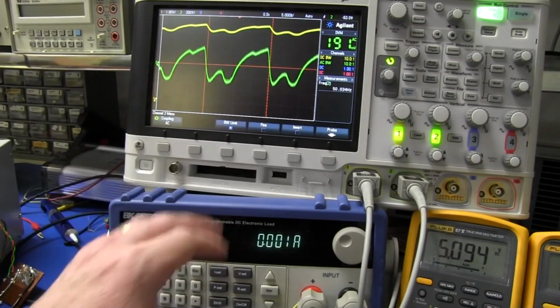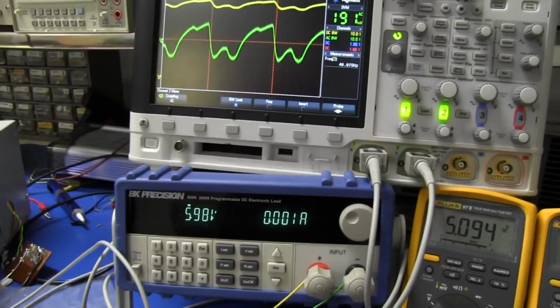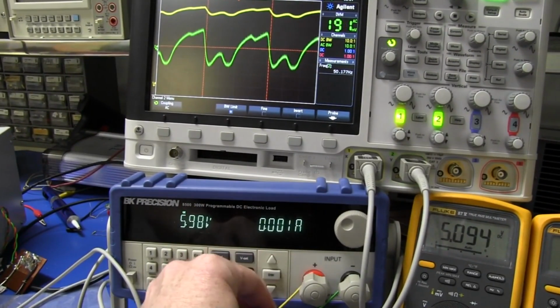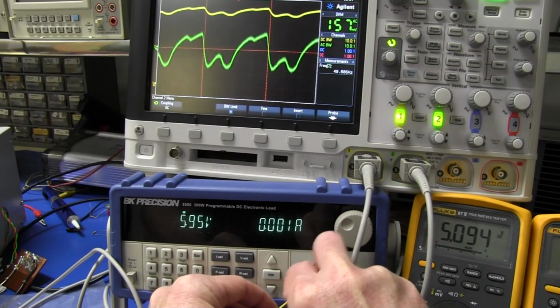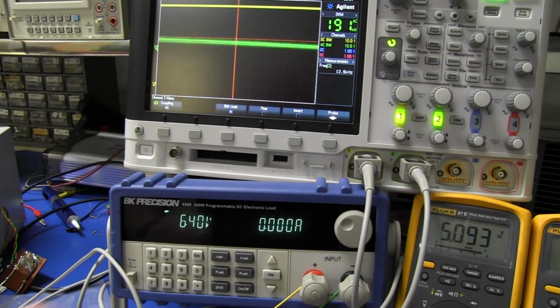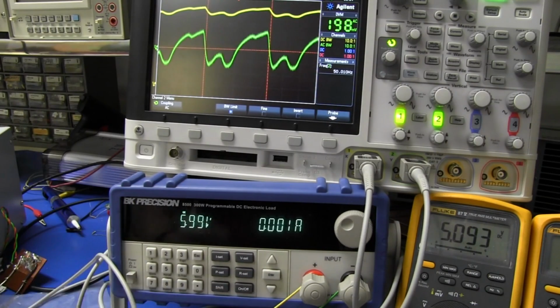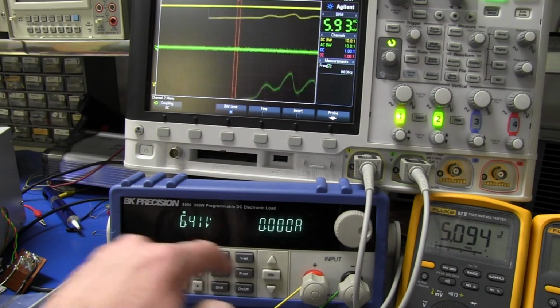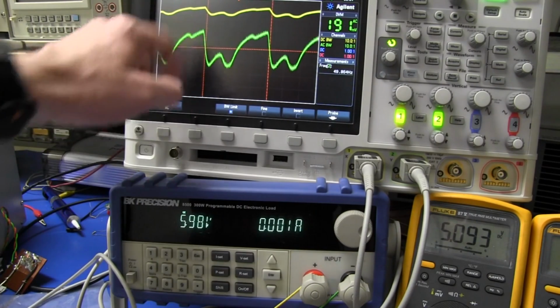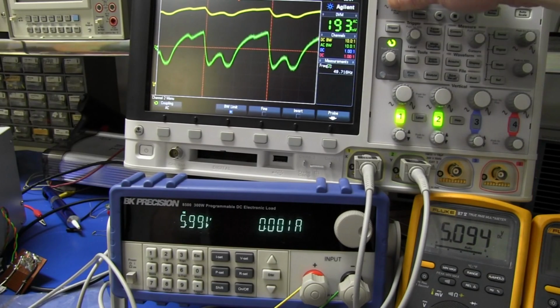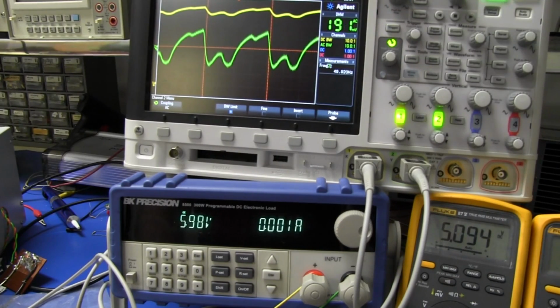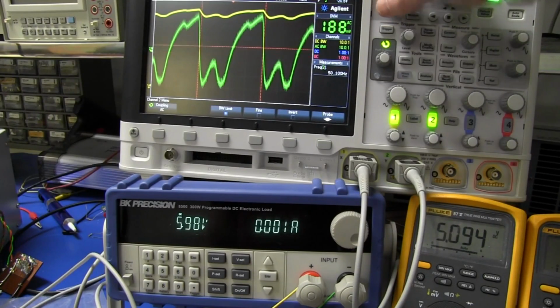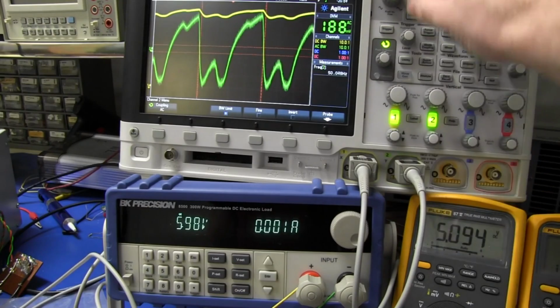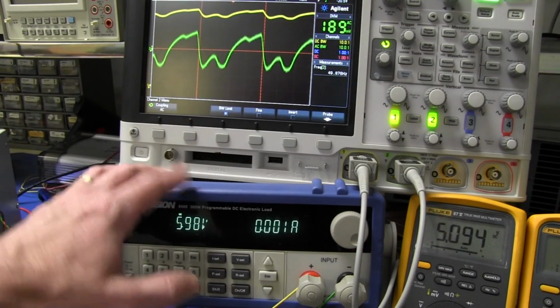Now as for this 50 Hertz issue with this electronic load, it's rather puzzling. If I disconnect it, it vanishes. If I switch it off, it vanishes. There's hardly any load - like 1 milliamp if anything, practically turned down to zero, but it really starts injecting massive amounts. We're talking 200 millivolts per division there, so 0.5 volt of 50 Hertz hum into our measurement system. Unfortunately I'm not able to get rid of that - it's just inherent in our test setup with this electronic load.